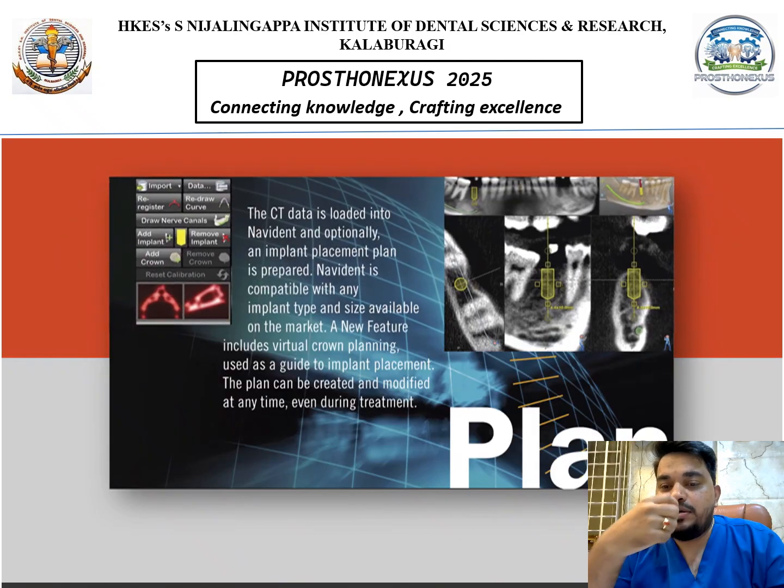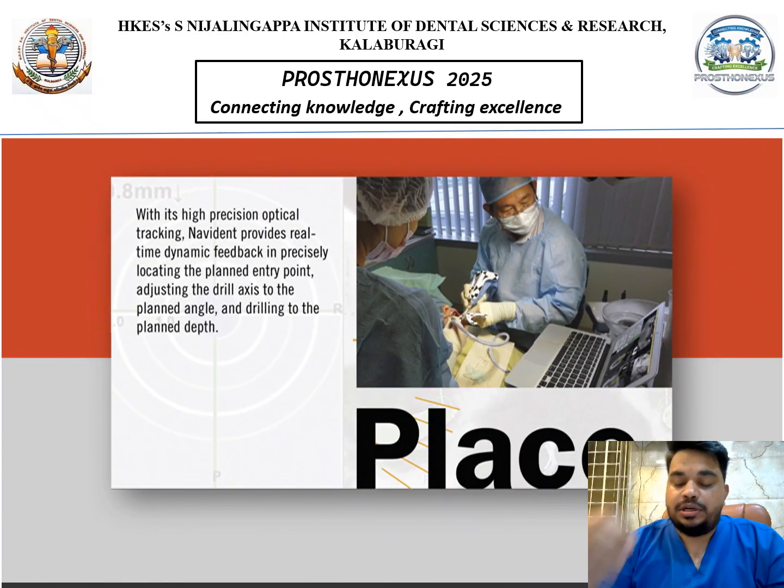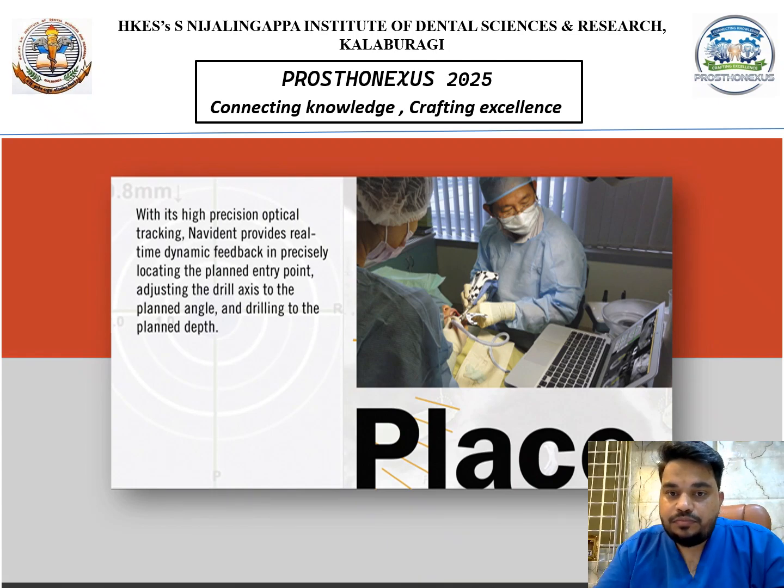Okay, we load that CT scanner information into our Navident software using this memory stick, and then we add this black and white tag to the instruments, calibrating the instruments, in the exact same place that we had the CT stent.